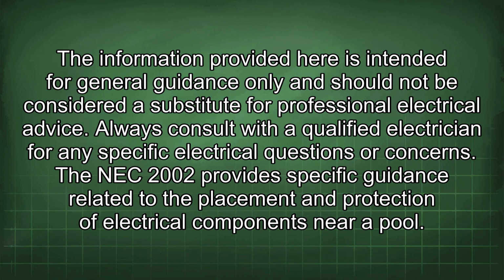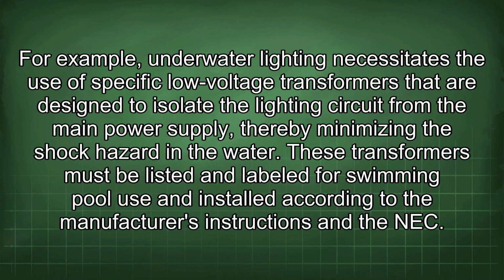The NEC 2002 provides specific guidance related to the placement and protection of electrical components near a pool. For example, underwater lighting necessitates the use of specific low-voltage transformers that are designed to isolate the lighting circuit from the main power supply, thereby minimizing the shock hazard in the water. These transformers must be listed and labeled for swimming pool use and installed according to the manufacturer's instructions and the NEC.